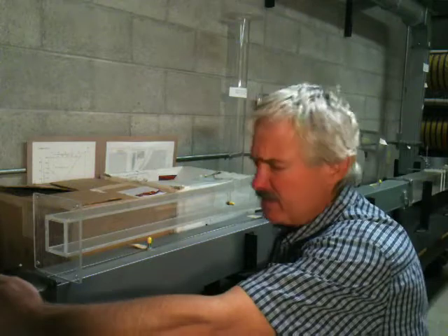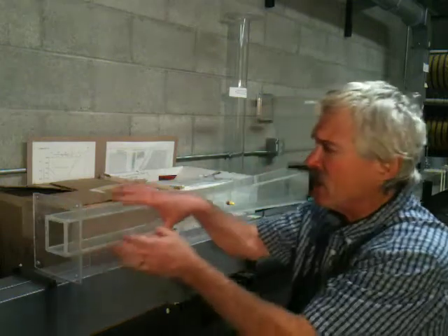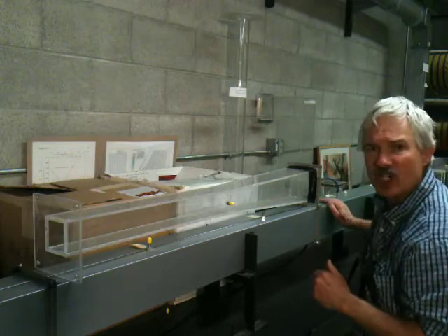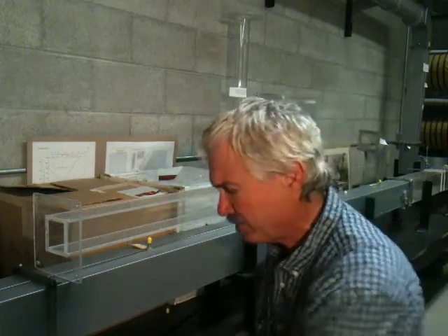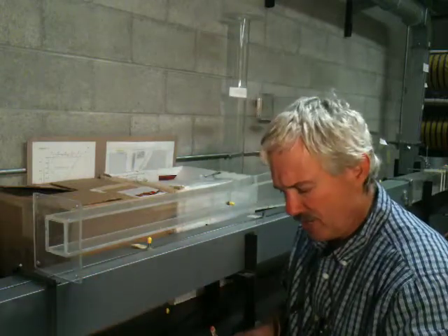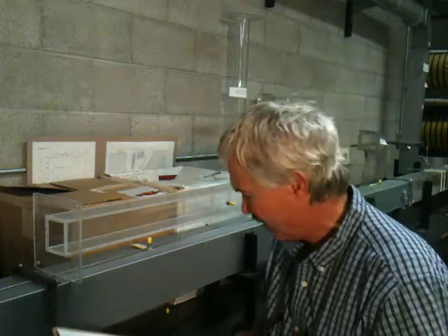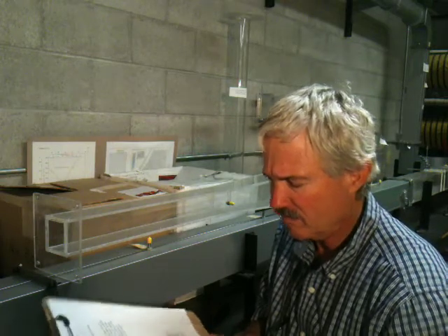Now air coming in, the original duct faces a sudden contraction here, flows through the smaller size duct, and then we have a gradual expansion back to the original size. So we've just reversed the order of the obstructions there. And in this case, taking the overall delta P from the upstream to the downstream side, delta P is 2.455 inches of water column, water gauge, and the velocity pressure is 0.395 inches. Okay, so there's those numbers.